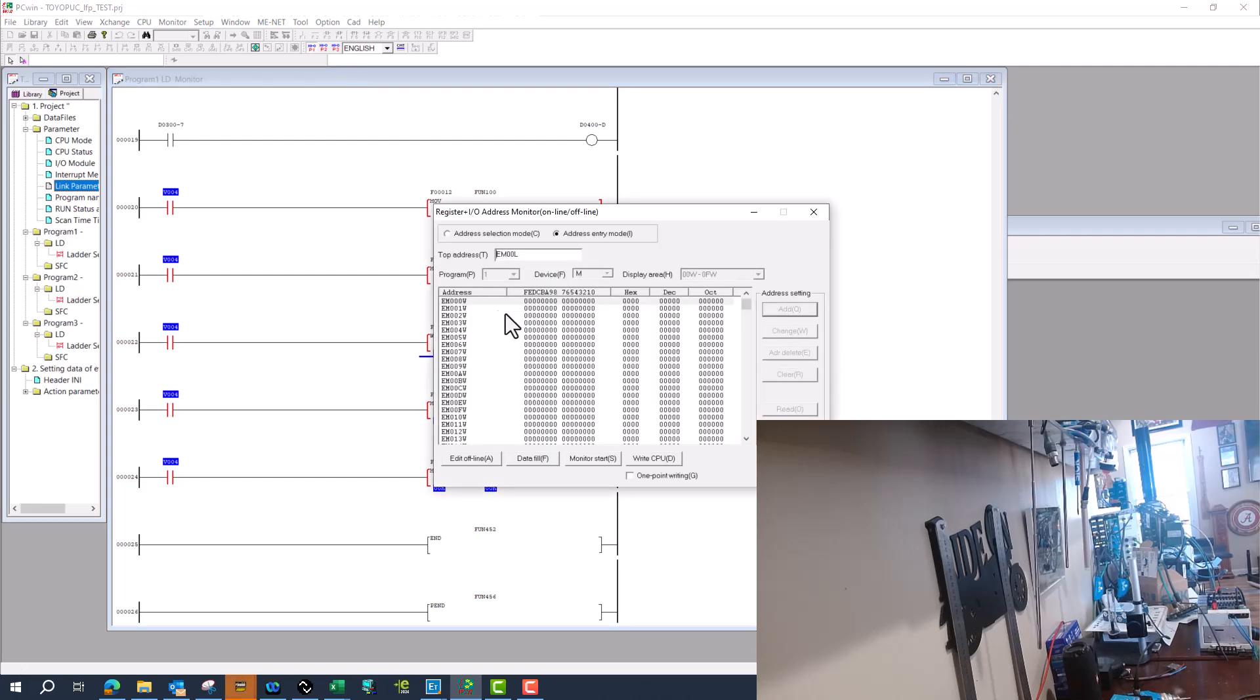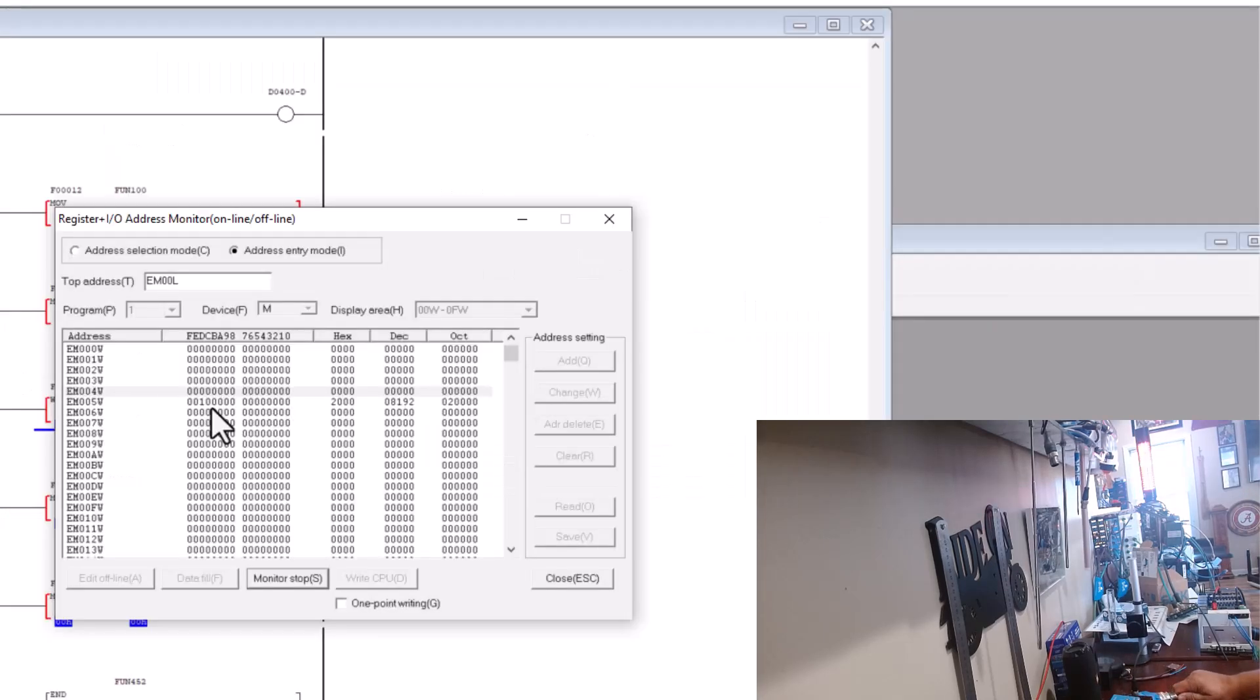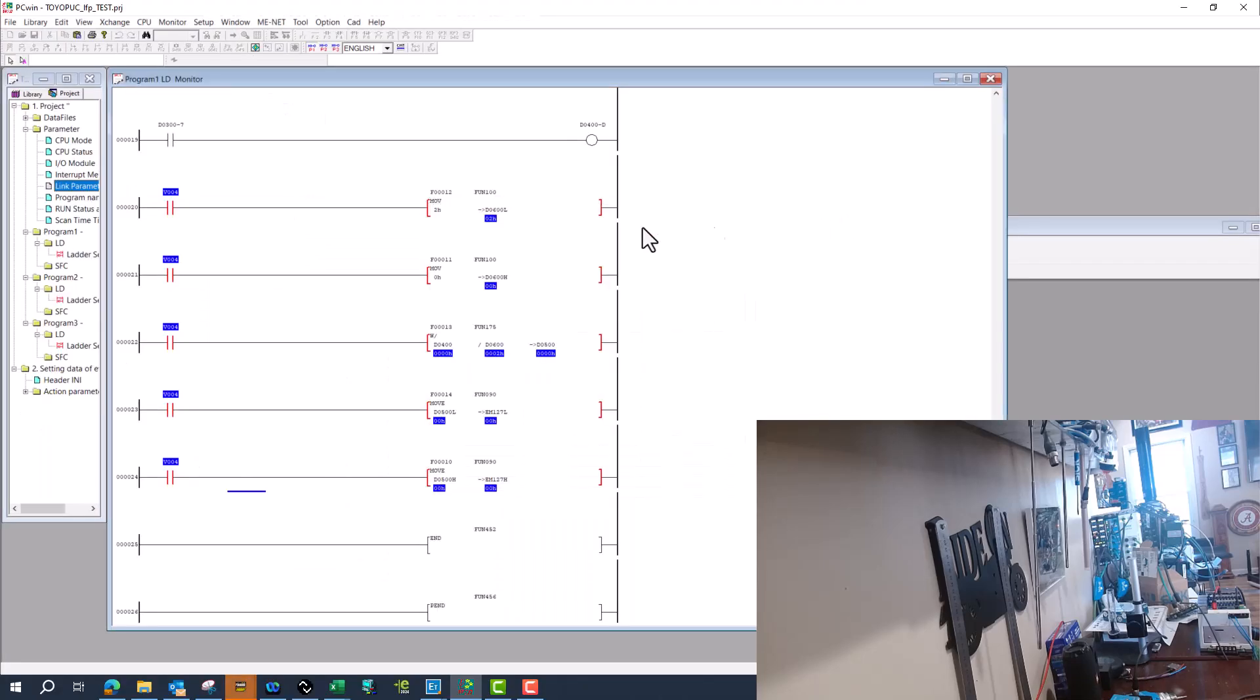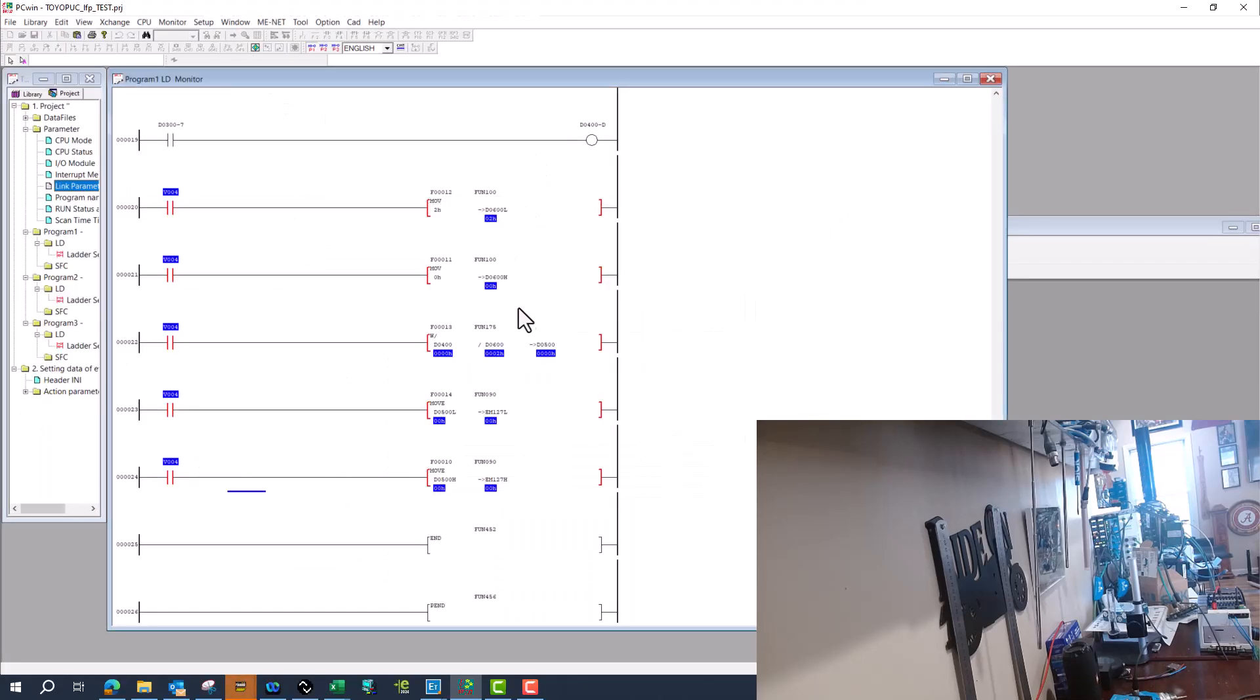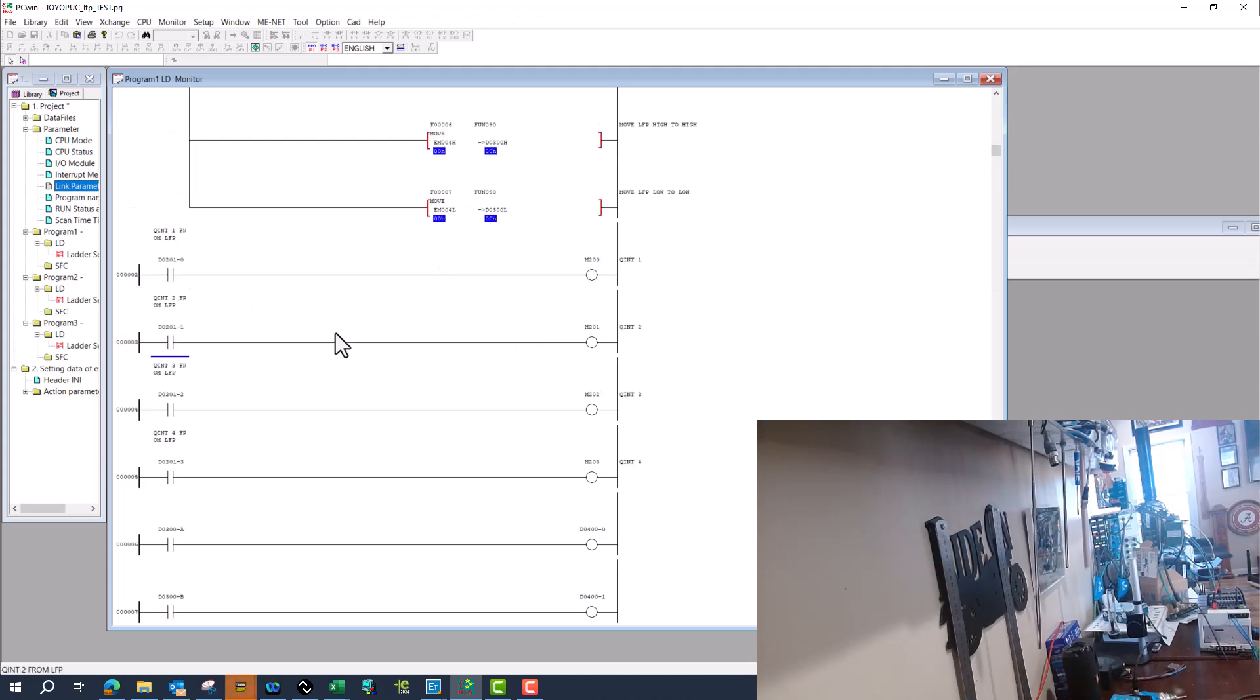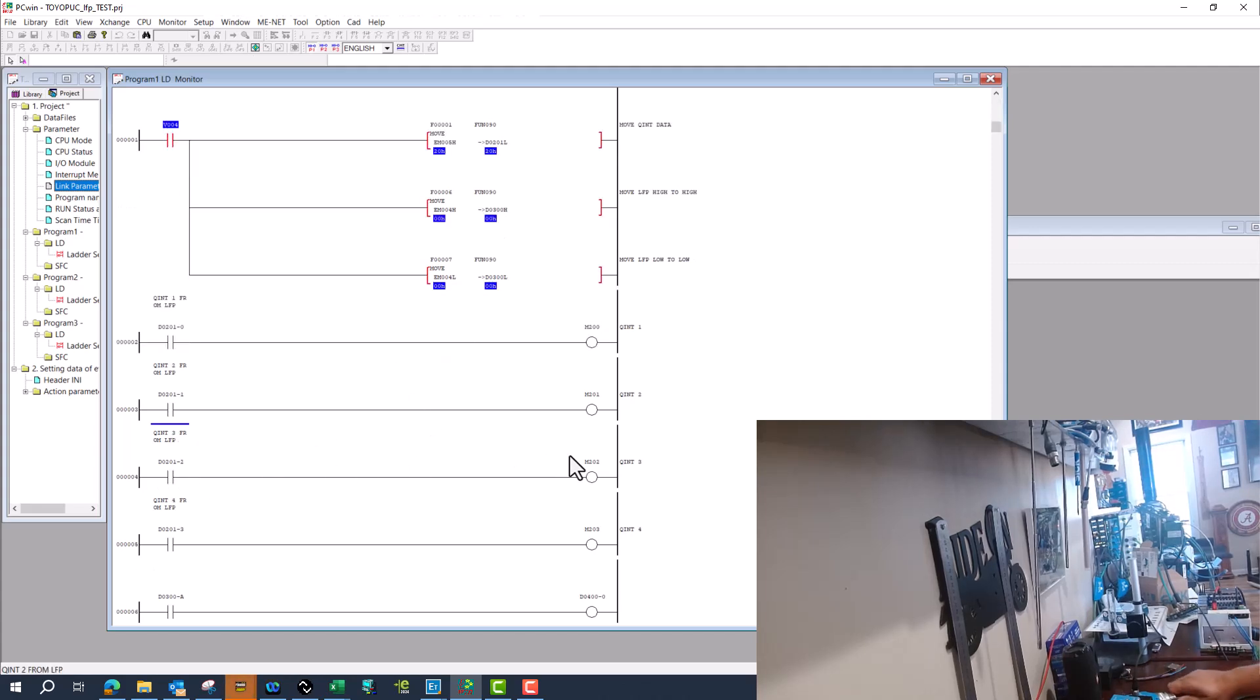So I started at 0. So 0, 1, 2, 3, 4, 5, 6, 7, 8. So that's how I knew exactly where that data was going to come in to start from my level. So now if you look here on the next word, now I'll get these four right here that are coming on. That's my Q-ints 1 through 4. So all it took was EM005, 8 through B. And that's how I got my Q-ints in right here. After I transferred the data. So I came from the high byte, and I moved it to 201 of the low byte, starting there. And then at 201, I just broke these out. And that gave me my four Q-ints.